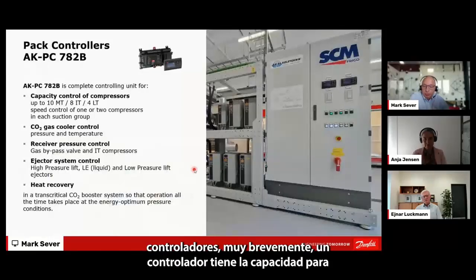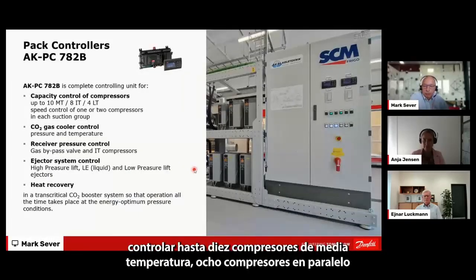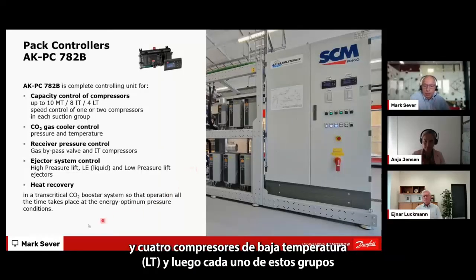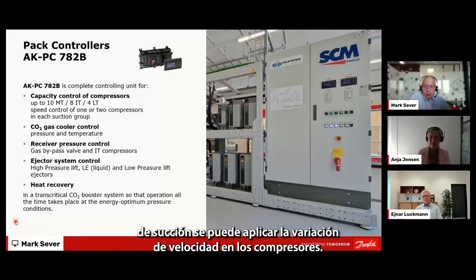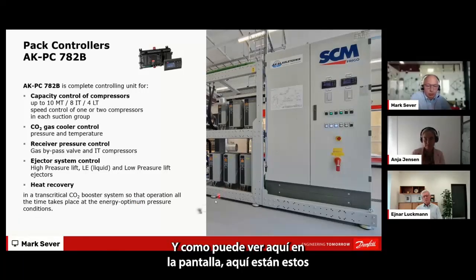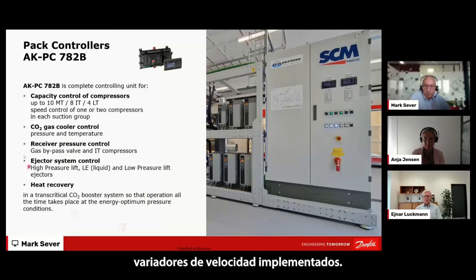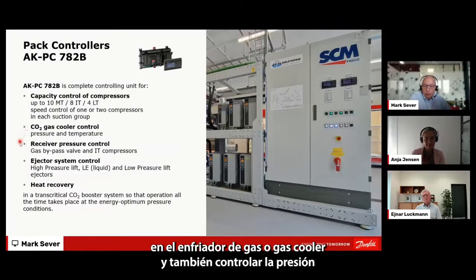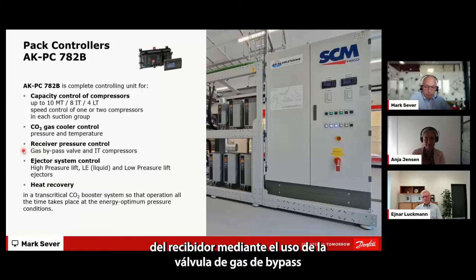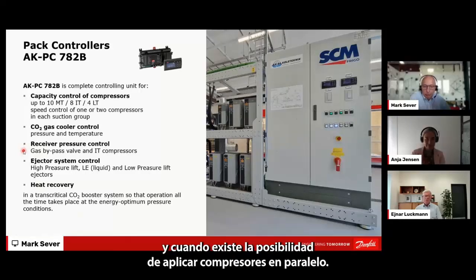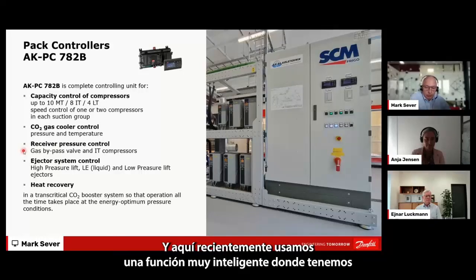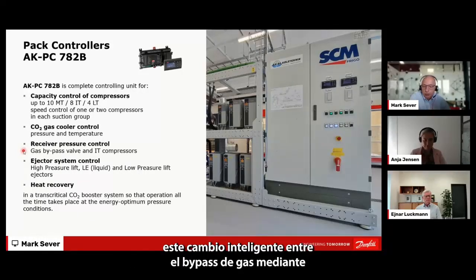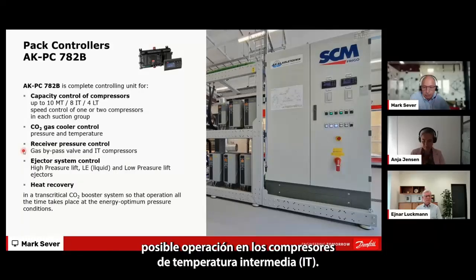Pack controllers, very briefly. One Pack controller has the capability to control up to 10 medium temperature compressors, 8 parallel compressors and 4 LT compressors, and in each of these suction groups we can apply 2 variable speed driven compressors, and as you can see here on the screen, all these drives are implemented here. Of course, this controller is controlling pressure and temperature in the gas cooler, and also controlling the receiver pressure by using the gas bypass valve. And when there is a possibility to apply parallel compressors, we recently introduced a very smart function, a smart switch between the gas bypass valve operation and the parallel compressors.